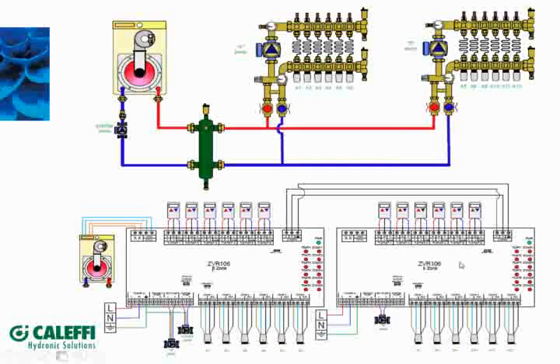This board will fire up its secondary pump. The secondary pump is related to the board that's getting the call for heat. So in this case, if this zone's calling, this pump is running, this pump is not running, and the system pump is running. So we're delivering fluid out to this zone out here and back. So the key to that is the B pump on the second manifold has to go to the B board.